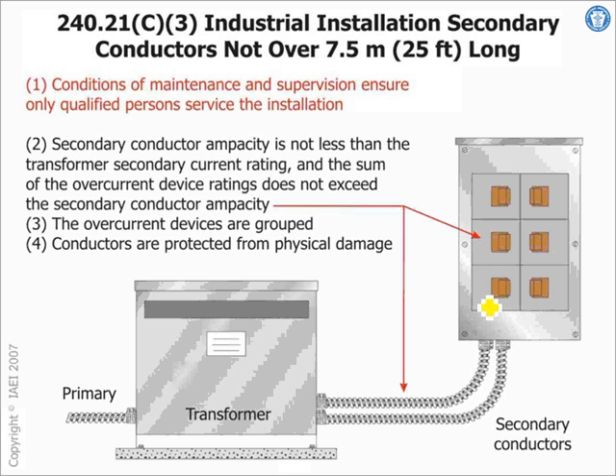In a case like this, we don't have any limitation. Again, with qualified people in an industrial installation, there is no limitation on the ampacity of the conductors, and no relationship between the overcurrent protection device ahead of them and the conductors. Again, this is a special application of 240.21 for industrial installations. So really, if you have a transformer in an industrial installation, technically you can take number 4 out and feed a load from it within 25 feet without worrying about what the primary of that transformer is, as long as you stay within 25 feet of the transformer, number 1, and number 2, as long as at the end of the conductor you put a circuit breaker to protect that conductor based on its ampacity.